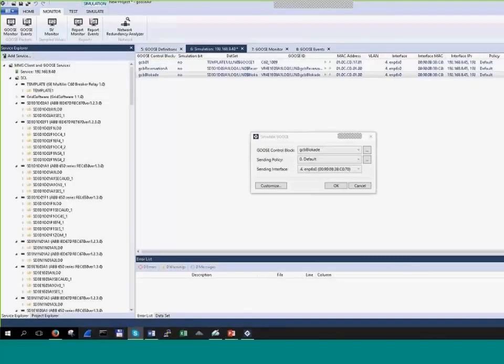I'm not talking about the structure of the goose message. I'm talking about the different flags and data. You can change only the data set. You cannot change any other parameters. That's the rule. But you could do it by creating your own SCL file and importing it, right? It is possible, but if you follow the standard, once you enable Goose, once you start the goose message, all properties are locked except the data set elements. The only parameter that can change is that you can disable it. But you have access to all the different data in the data set. Yes, exactly. That you are allowed.